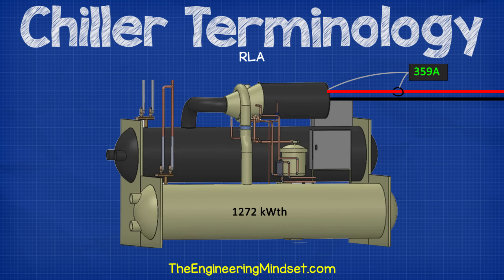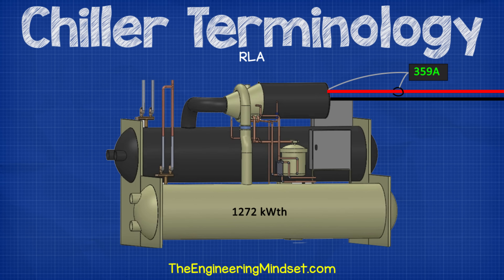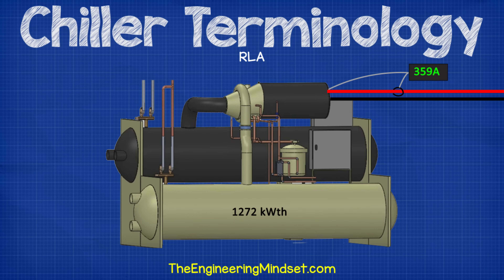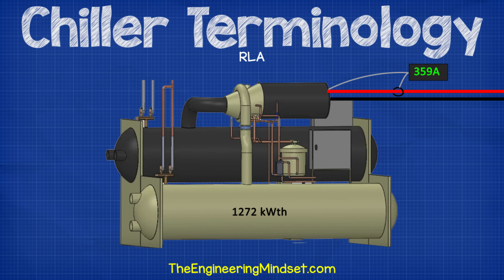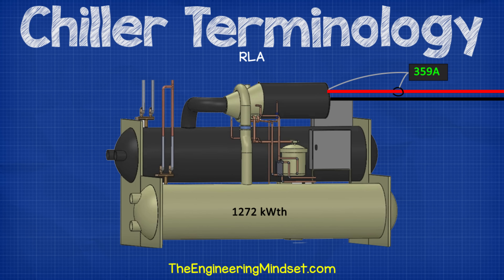Rated load amps, or RLA. RLA refers to the maximum amps drawn by the compressor's motor during operation. The RLA will vary depending on how much work the compressor has to do. If the RLA is exceeded, then the compressor motor can overheat and destroy itself. There are safety features built into the chiller's controls to measure and prevent this from occurring. For example, a 1,272-kilowatt rated centrifugal-type water-cooled chiller has an RLA of 359 amps, but the chiller will cut the power to the motor if it reaches 455 amps. This limit and value will vary between chillers and manufacturers.